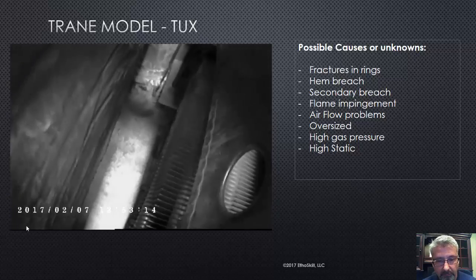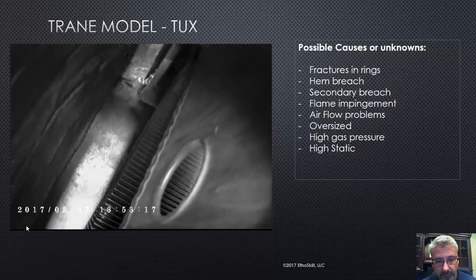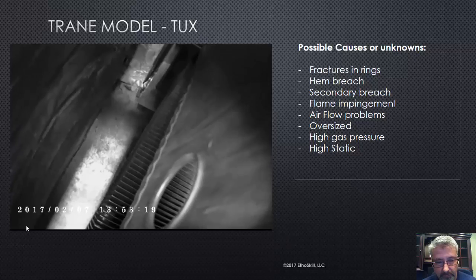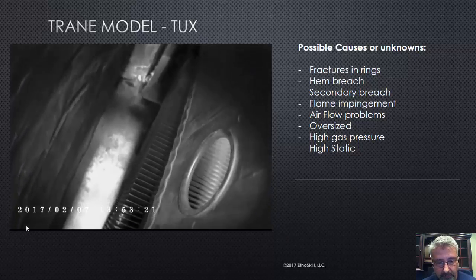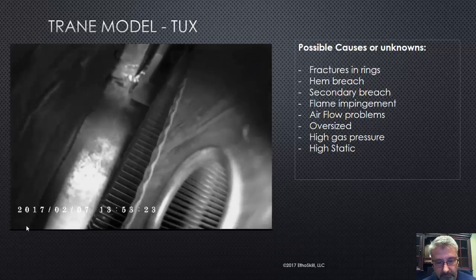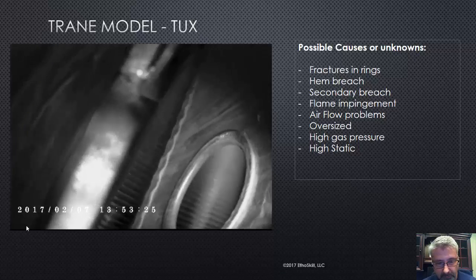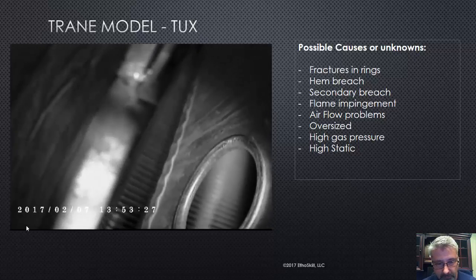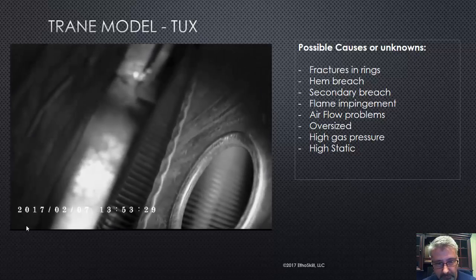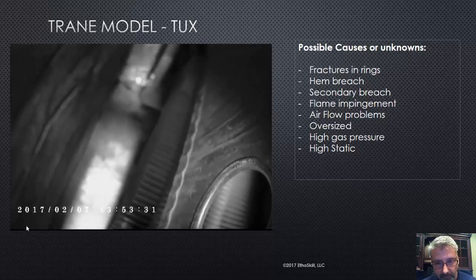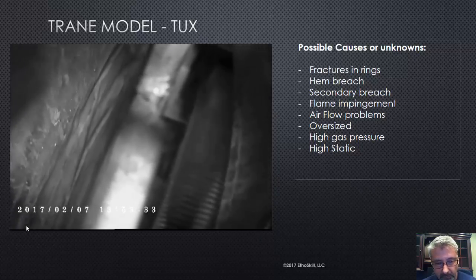And remember, condensing gas furnaces are under negative pressure. That primary is under negative pressure. So if you have a breach in that ring, and it looks like there might be a tiny little hairline fracture in that one, very difficult to see. But again, if you start drawing air through that primary, you're going to have issues.